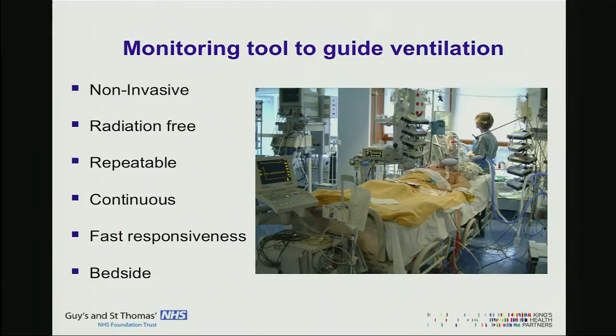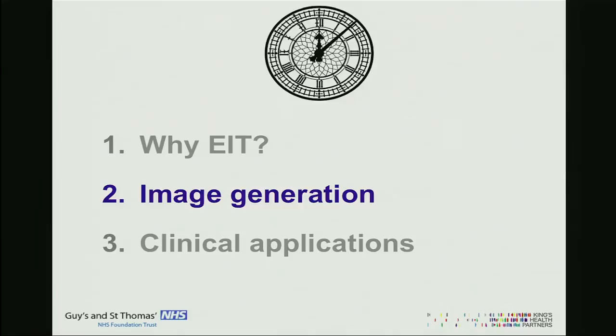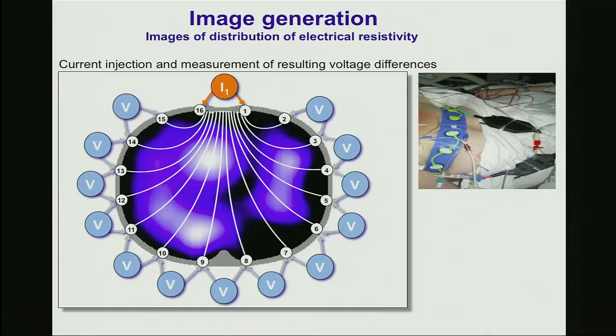How can EIT generate an image and what is an EIT image? The image that EIT generates indicates a distribution of electrical resistivity or impedance — I'm going to use resistivity and impedance as the same concept. Impedance for lung EIT is actually proportional to lung volume; it's the amount of air in the lung that stops electricity going through. We can measure that non-invasively with a rubber band and 16 electrodes around the chest, where each electrode has a significant contribution in the generation of the image.